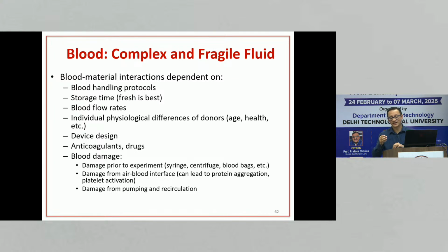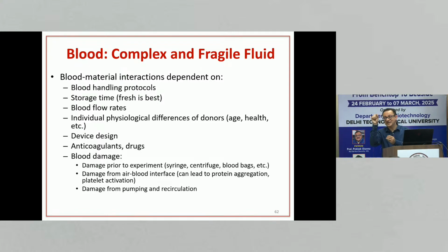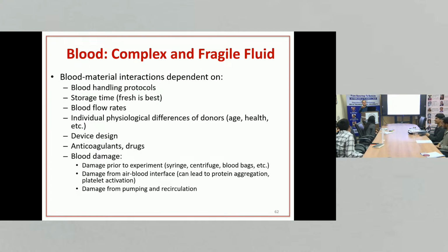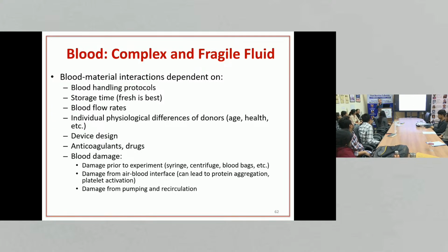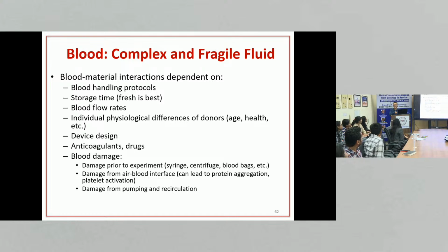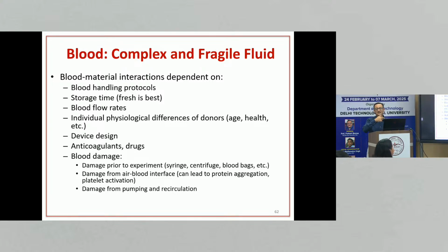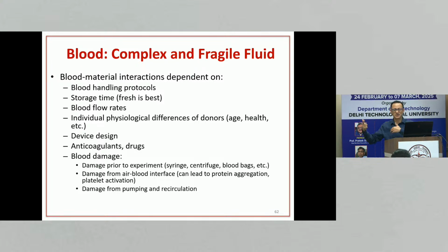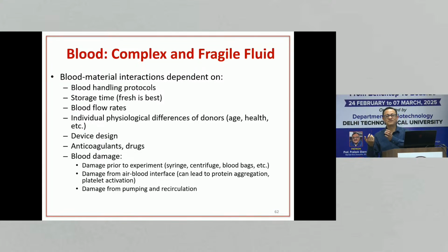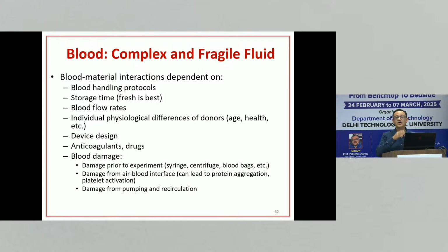Wow, that's such a dream, right? Isn't that why we are designing these devices, so that nothing clots on the tubing? If you are using an ECMO machine, we have to add heparin to the blood, so you have so much heparin that it's preventing anything from clotting. But if we want to go away from heparin or reduce heparin, we need to design surfaces that will prevent any clotting from happening. That's paradoxical. Yes.